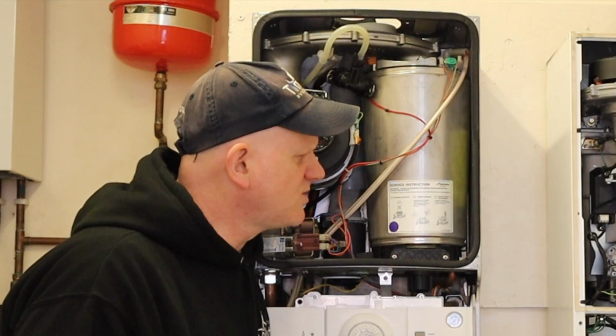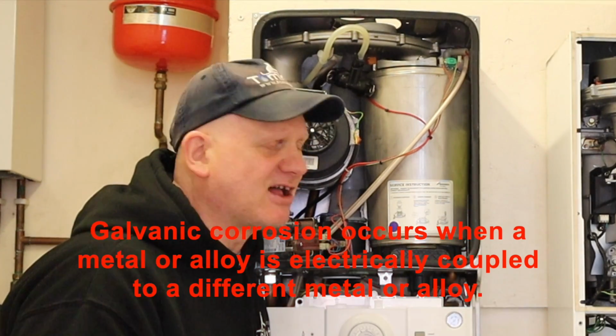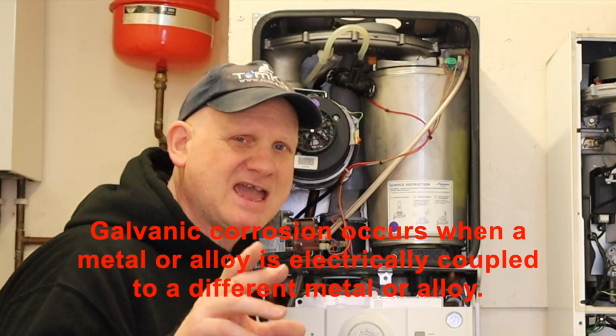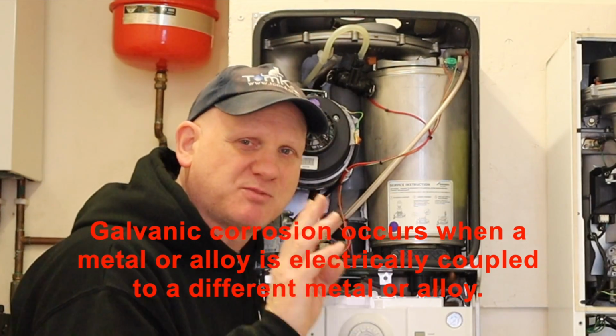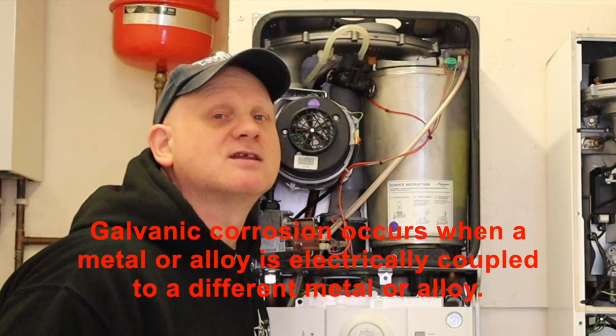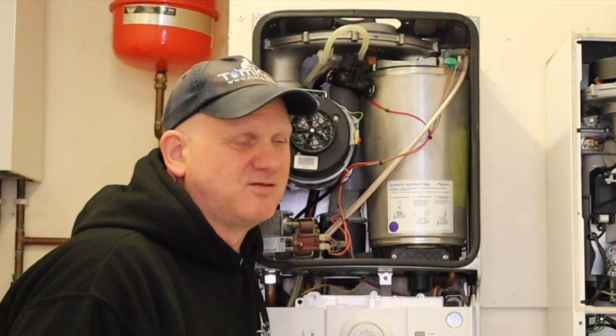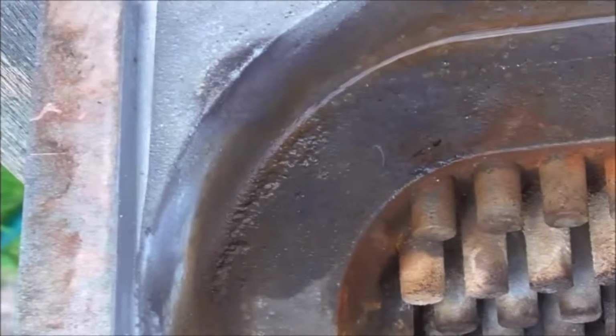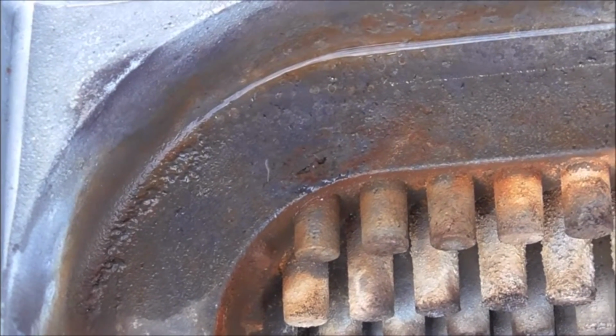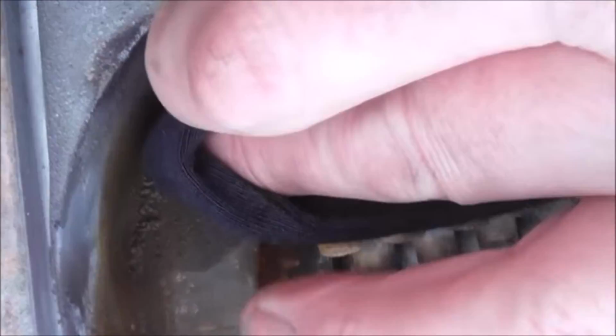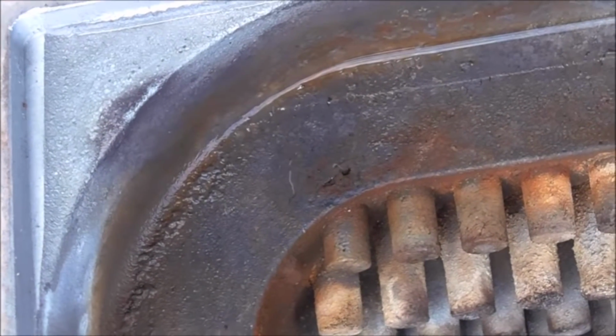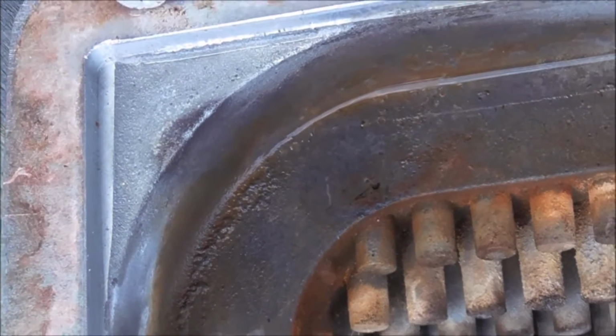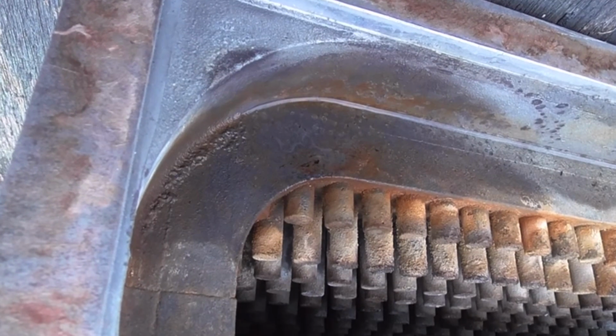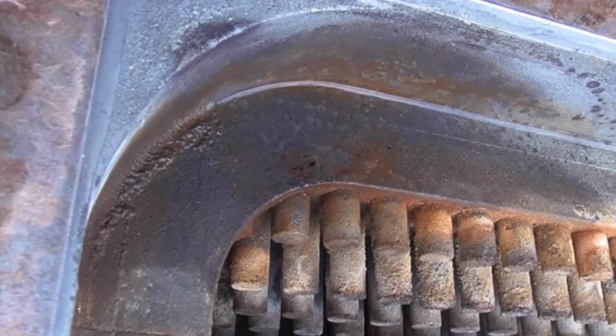But one of the major downsides of an aluminium heat exchanger is galvanic corrosion. And the pH levels in the water must be kept perfect. Otherwise, these heat exchangers start to pinhole and corrode. So that's one of the major downsides of them, but we'll talk about pH in a minute. Now this is an Ideal aluminium heat exchanger, and you can just start to see here water coming through the heat exchanger where it's corroded. If you look very closely, you can just see the water on the edge and where it's starting to pit and corrode here.